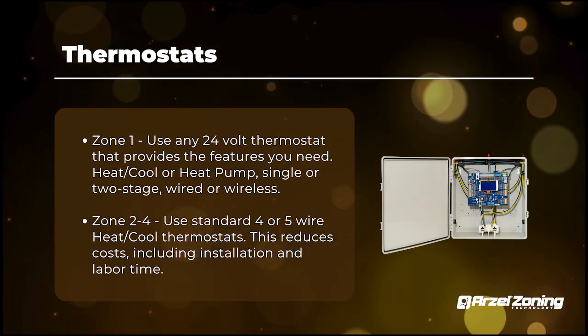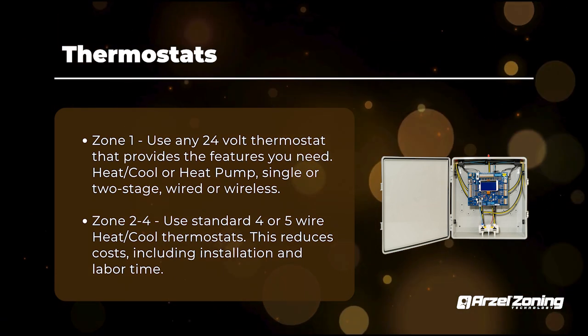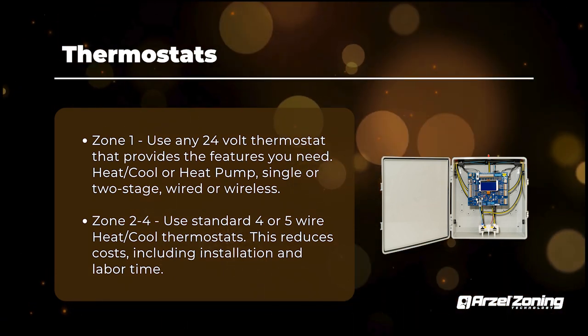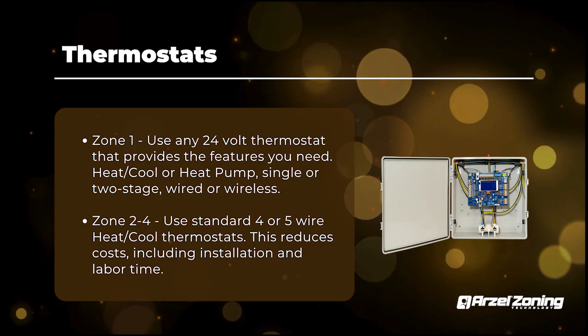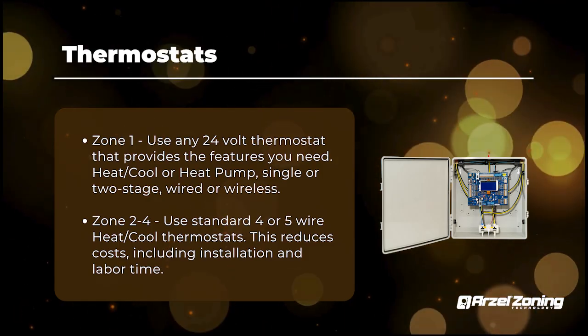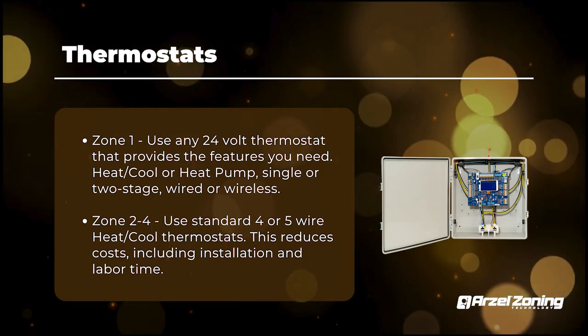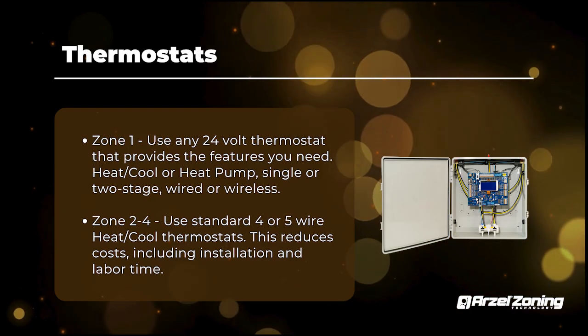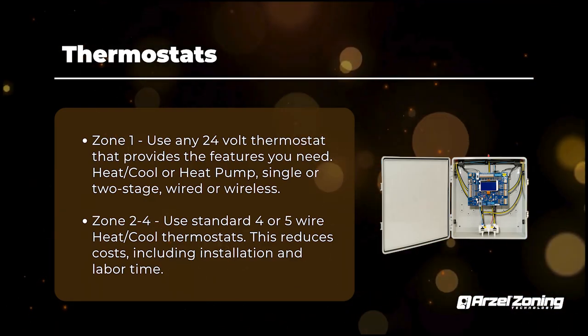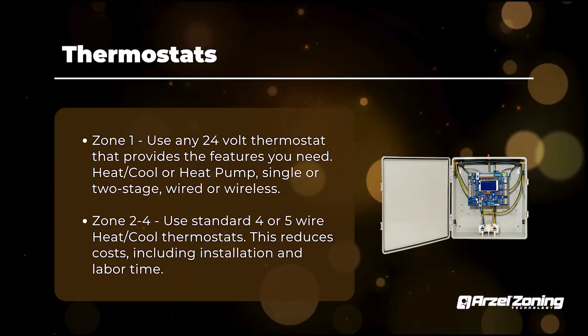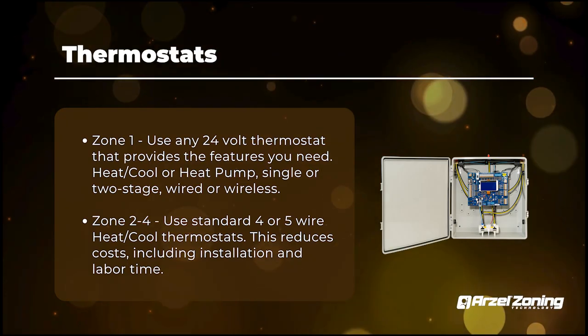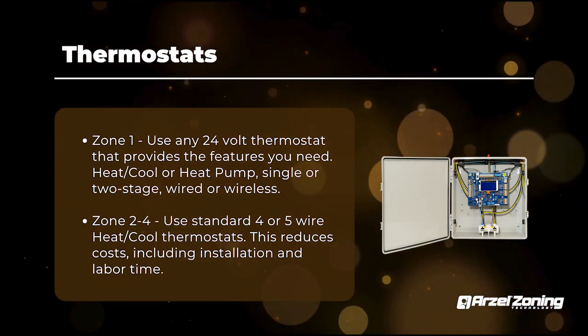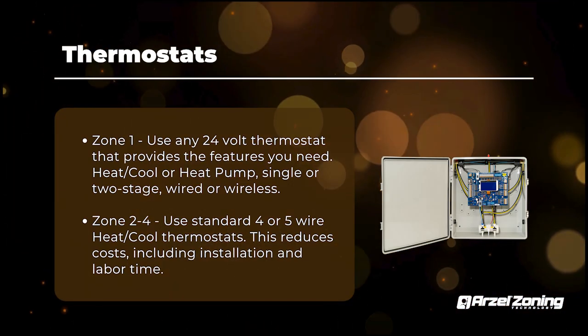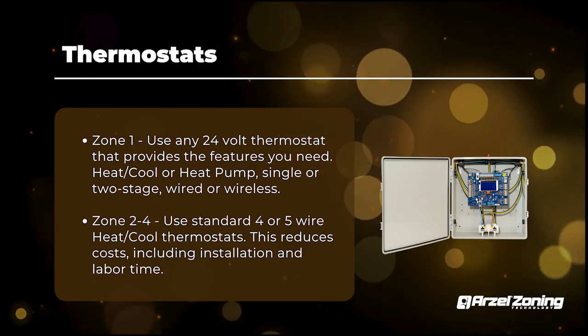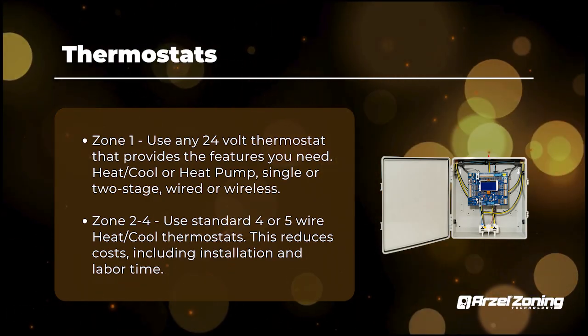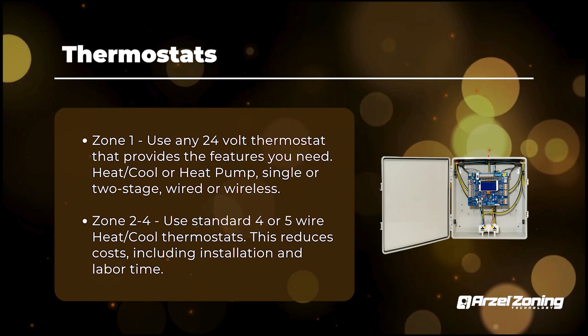So really depends on how you guys want to set it up. Most of us in tech support will tell you to use just heat cool thermostats. It takes all the brains away from the stat, gives complete control over to the panel, and you'll have better, more efficient equipment operation that way, because it's maintaining those ductwork leaving air temperatures, and it's going to stage that equipment based on an overall temperature rather than just that area of the home. So that's typically what we recommend you guys do, heat cool stats on all zones, but it does give you the option if you guys want to go ahead and use heat pump stats.